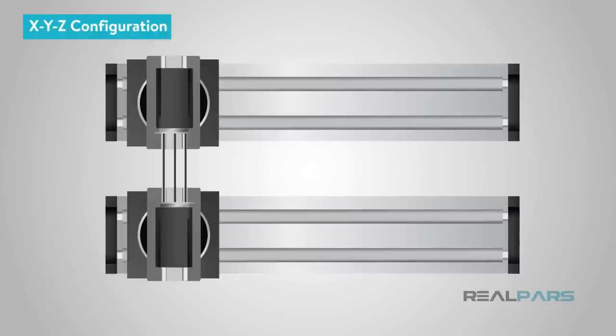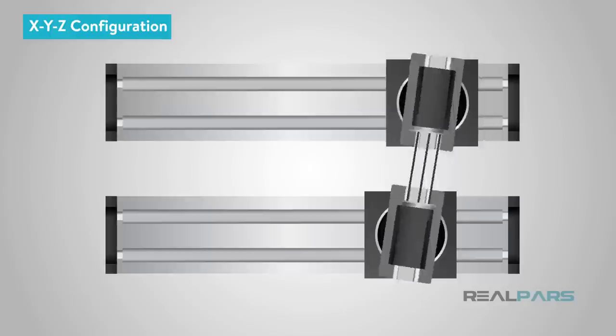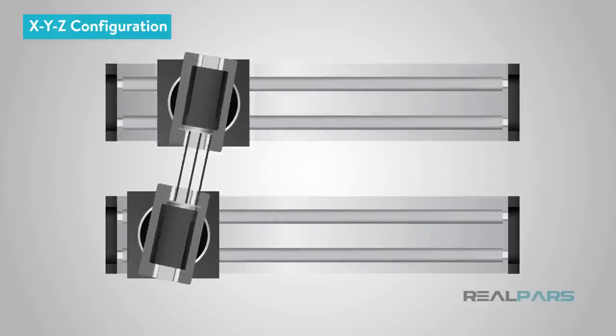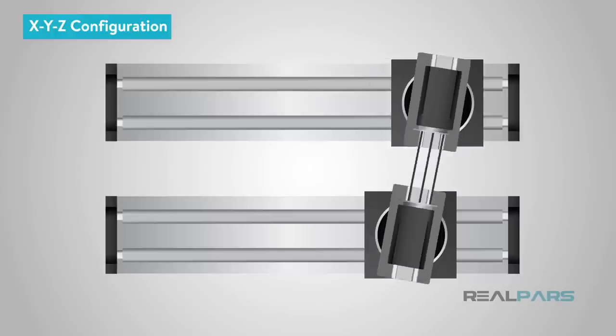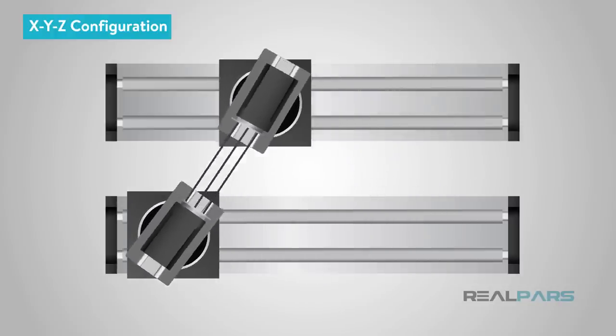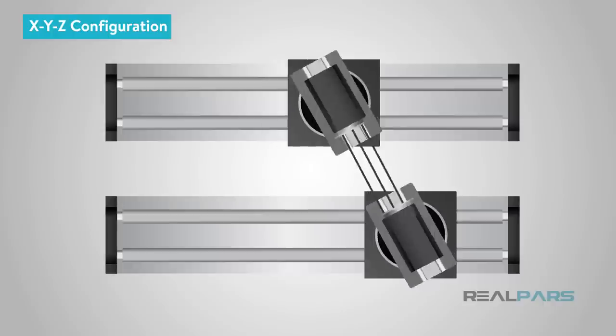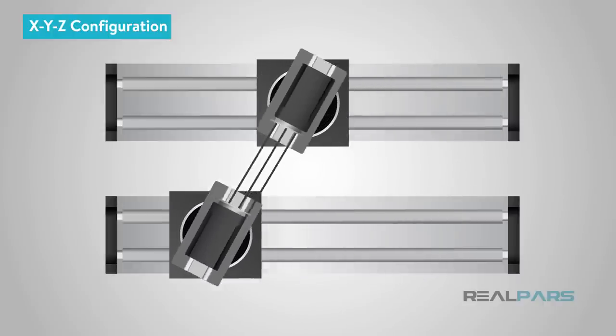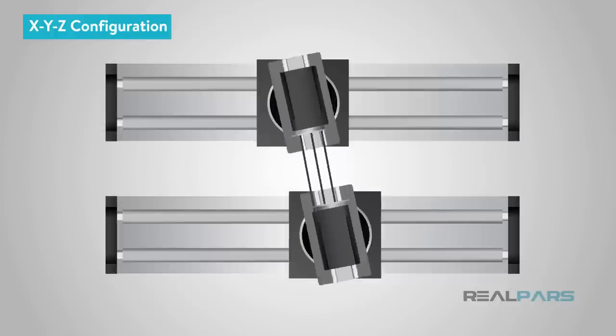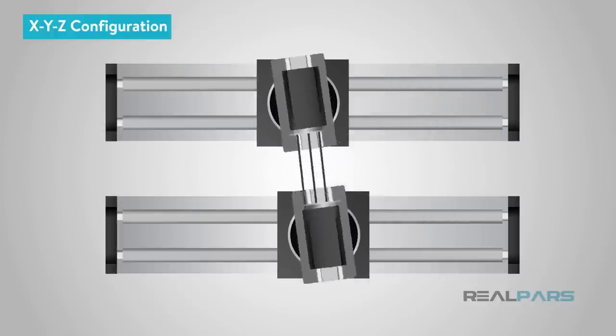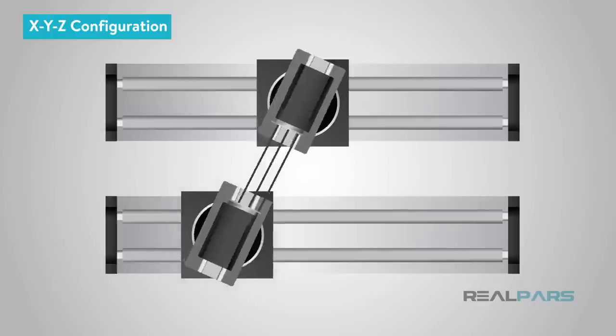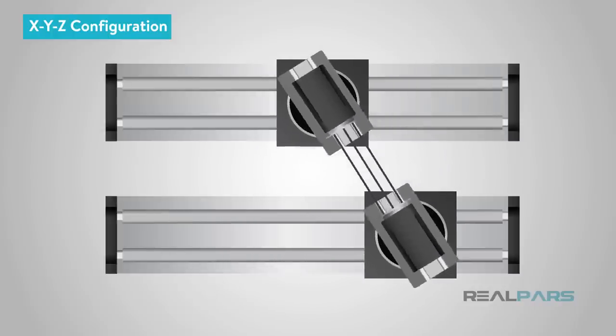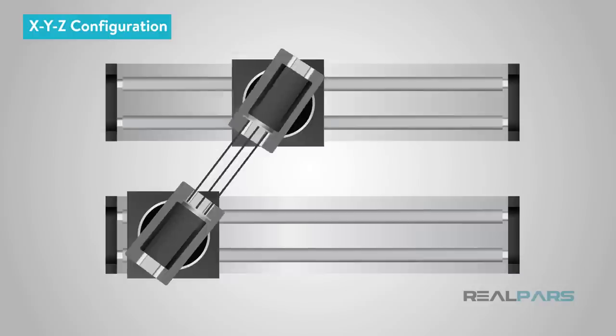Factors to consider here include the direction of travel of each axis. Does the load need to be moved simultaneously in multiple axes, or does each axis move individually, and does the system require a moving carriage or a moving rail, and are the axes vertical, horizontal, or inclined? And finally, are the mounting positions of each actuator at zero, 90, or 180 degrees to the horizontal.